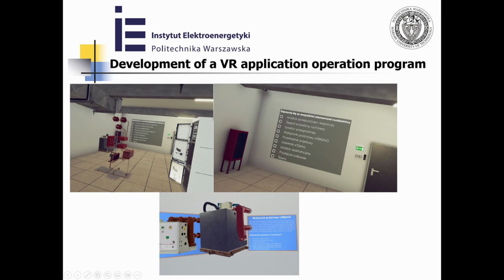In order to open the withdrawable compartment of the switchgear, it was first necessary to release the lock preventing the opening of the compartment door in the absence of safe conditions. This is done by opening the circuit breaker contacts, pressing the red button responsible for controlling the circuit breaker, and closing the earthing switch by means of the green earthing switch control button. If incorrect steps are taken, the user is notified of the inability to perform them.